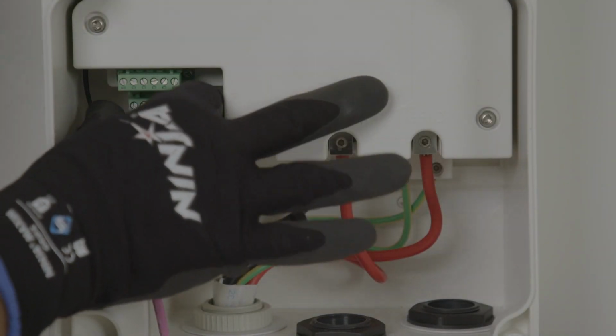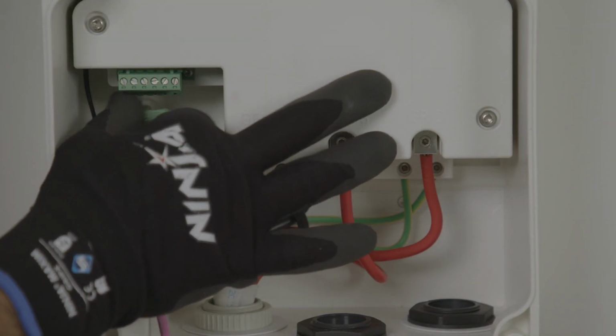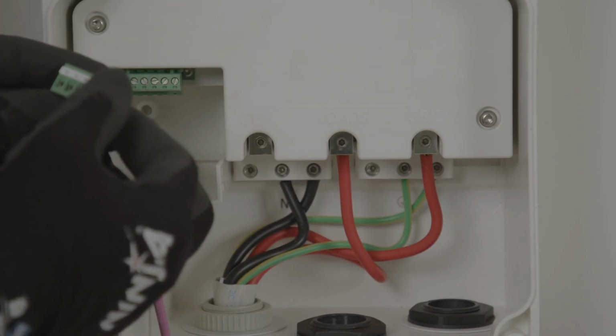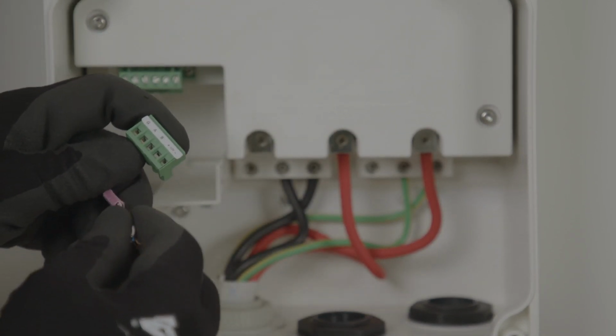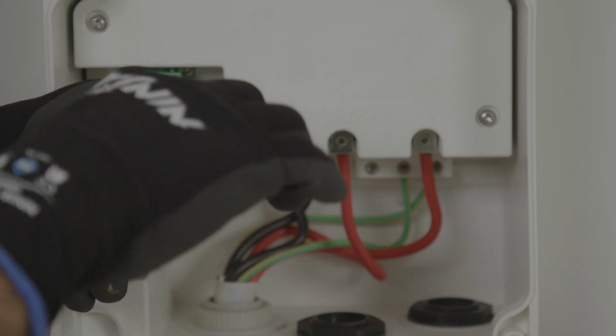So the backup interface requires a comms connection between itself and the Energy Hub inverter. So you need to wire the ground, A and B connections, as well as a 12 volt power supply.